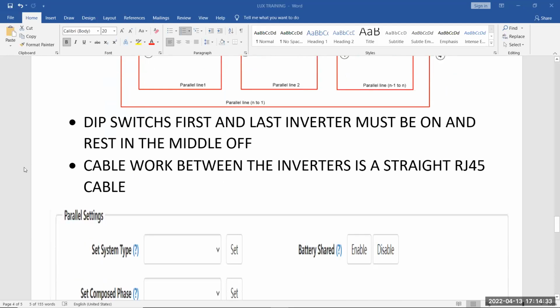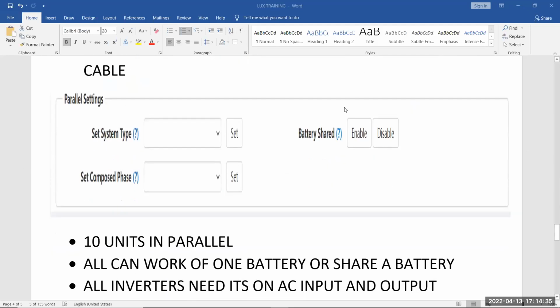Now, this is where you do the parallel settings, where I showed you online. If it's a single phase system, all of them will just be single phase parallel. Then batteries on these inverters that share: we recommend that you use the same battery bank for all your inverters in a parallel system. So this means you can have 3 inverters pulling power from the same battery.